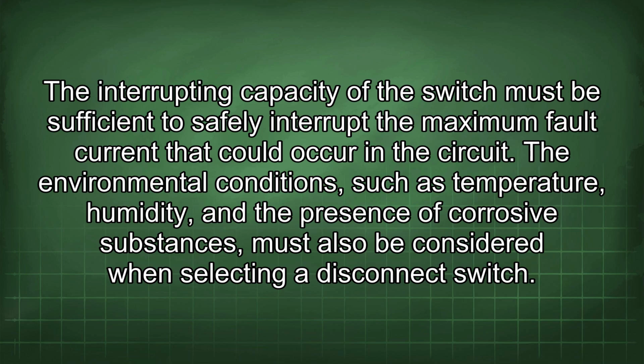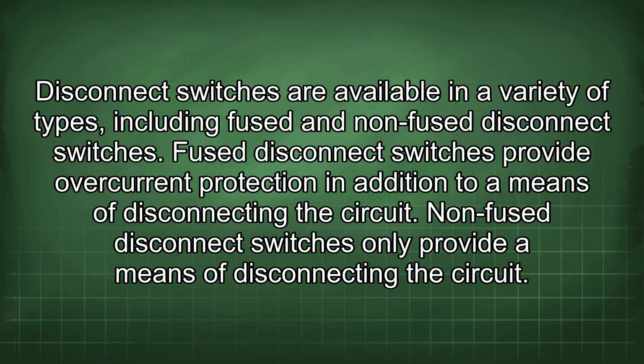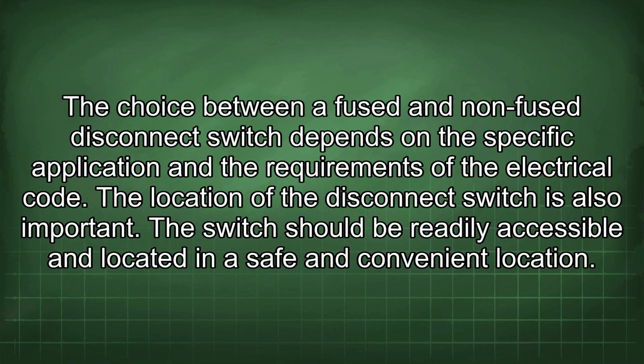selecting a disconnect switch. Disconnect switches are available in a variety of types, including fused and non-fused disconnect switches. Fused disconnect switches provide overcurrent protection in addition to a means of disconnecting the circuit. Non-fused disconnect switches only provide a means of disconnecting the circuit. The choice between a fused and non-fused disconnect switch depends on the specific application and the requirements of the electrical code. The location of the disconnect switch is also important.